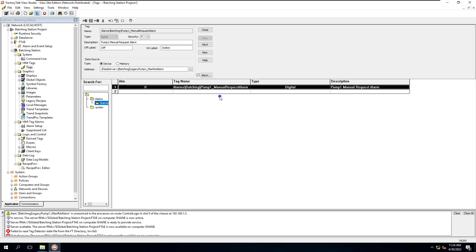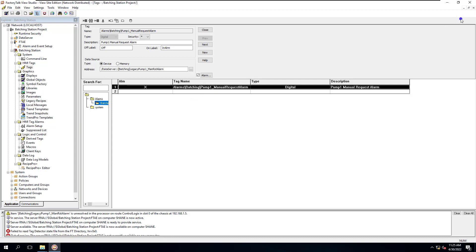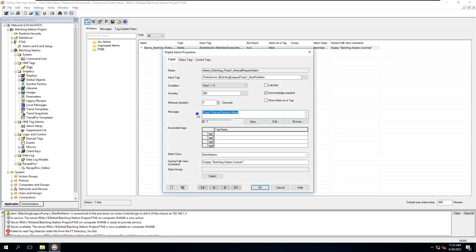However, if you're using this tag and try to delete it while on an active system, it's not going to allow you to delete it. You need to disconnect all your connections and then delete it. Right now I can delete this very easily because I'm not connected to my actual running system. If you are connected to a live system and this tag is actively connected, you'll have to disconnect — whether separating redundancy, primary from secondary, or just briefly separating from PLC connections. The migration does a full conversion: the alarm message and display from your legacy tags will already be carried over.